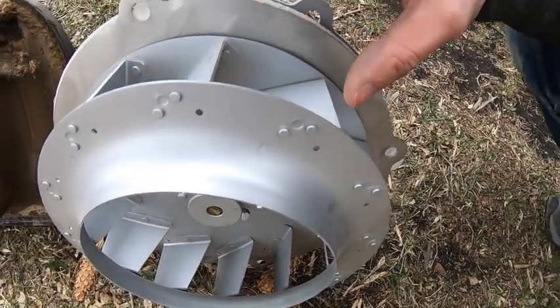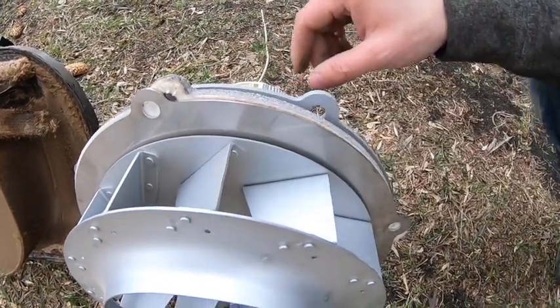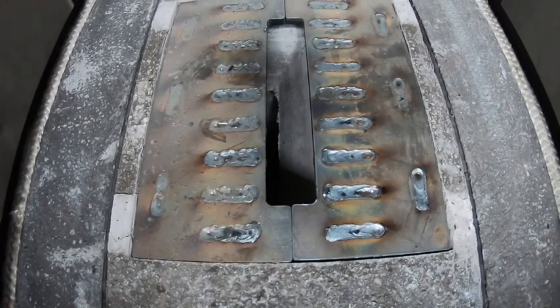Okay. So the ECM motor is what I feel makes this furnace work as well as it does. If there's a blockage on the nozzle, it will ramp up to try to clear it. So that without any extra electronics, the motor's able to do that on its own. It's going to have the lowest energy consumption and also very powerful. It's also going to last 2 to 3 times longer than a conventional suction fan.